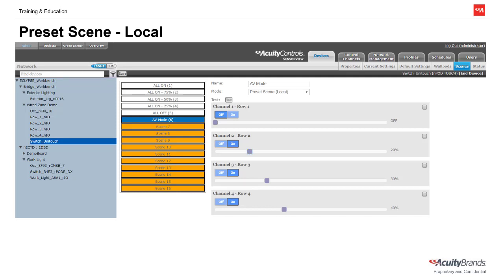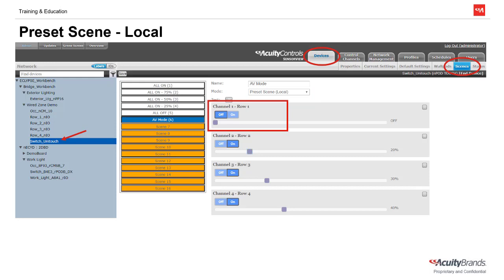Let's take a look at a local preset scene. As you can see in Sensor View, we're in the Devices tab and then in the Scenes tab of an nPod Touch. If this were another type of device, the Scenes tab would instead be default settings. We'll use our AV mode scenario from earlier. Since we only want to manipulate lighting levels only, we'll select the mode to Preset Scene Local. Now available in a drop-down menu will be all of the switch channels that the lights are tracking. Note that these switch channels have already been programmed on the Controls Channels tab, which is why you see them here.